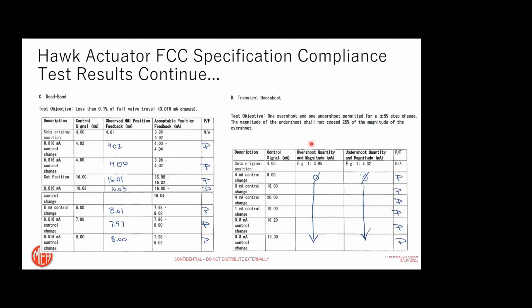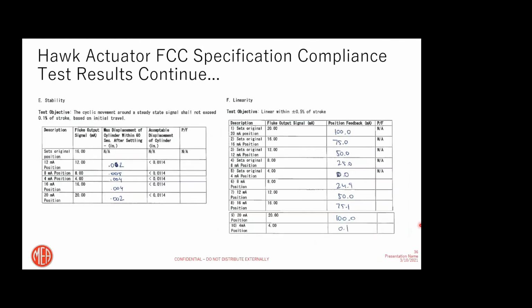We met the required requirement. Transient overshoot, same thing. Basically, every time we position the valve, it landed right into the dead band. So it's a 0 overshoot and passed every single time. Stability, these numbers are about 5 times better than what's required, but I would consider this more as an error rather than any real movement. Same thing with the linearity. Every single time the actuator positioned within 0.1% of the stroke, for all 4 actuators.